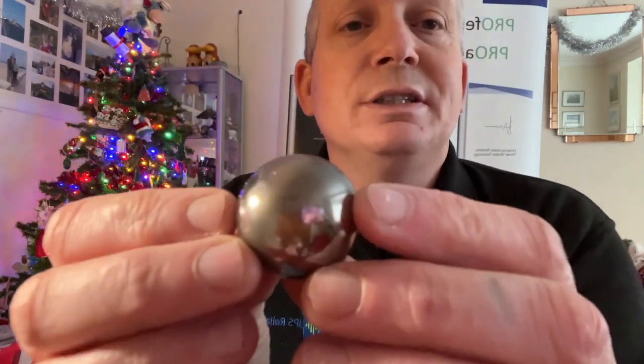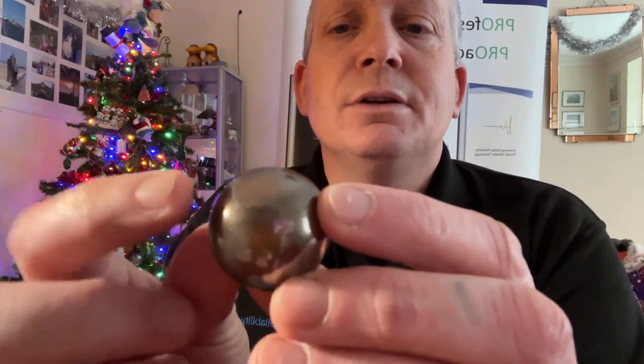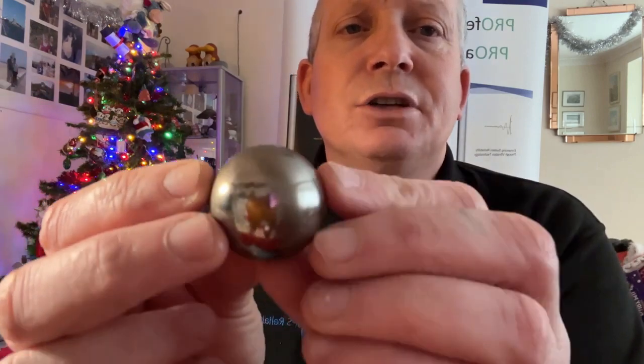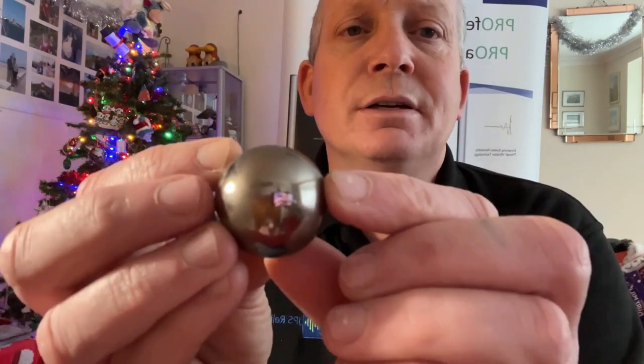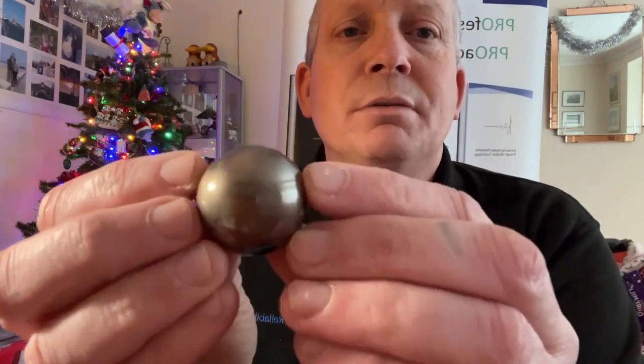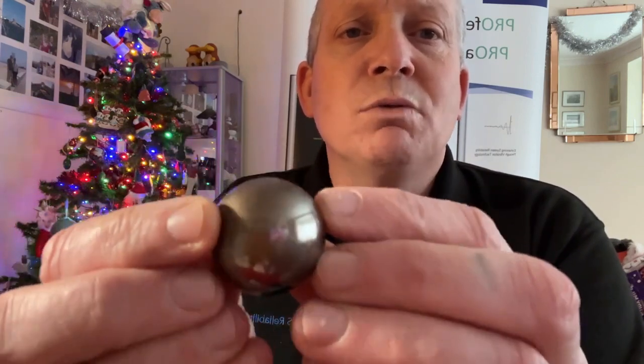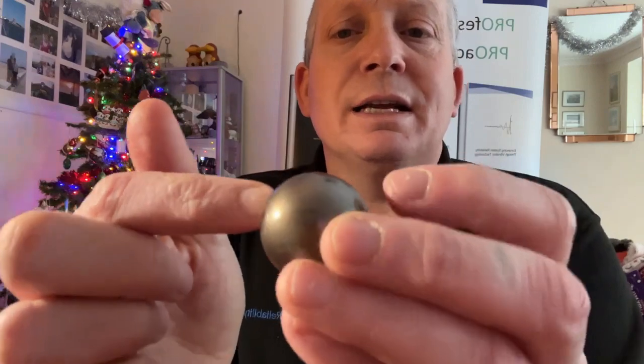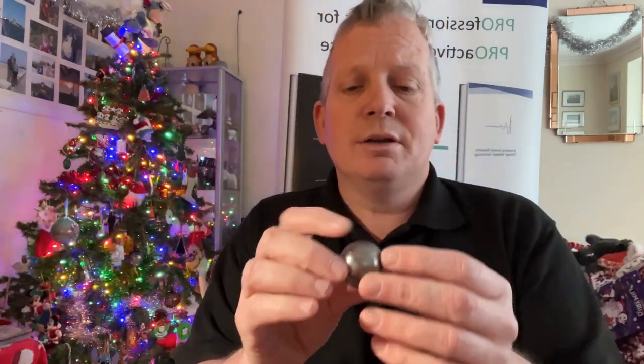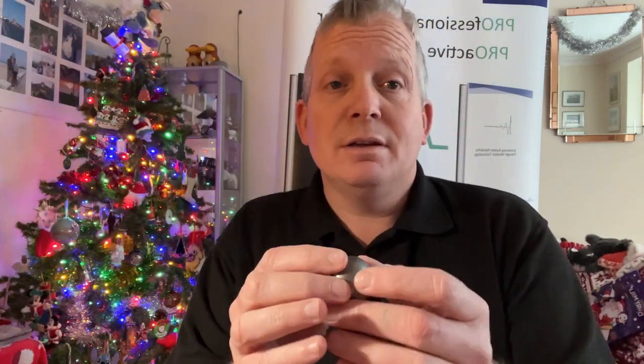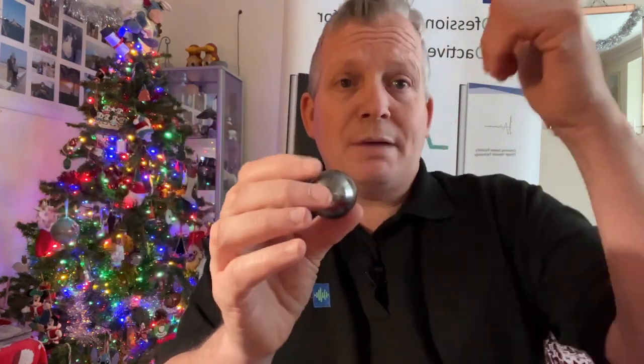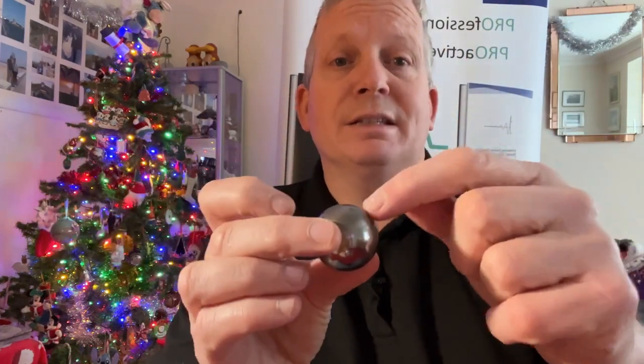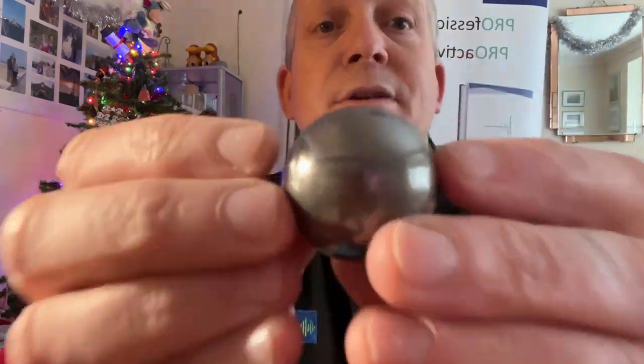Okay. Now, another giveaway if you've got drive problems or challenges: if you look at the rolling element here, you can see it's shiny there, but then look at this bit here. It's got a row of dullness. That dullness is the electrical high frequency current, noise, whatever you want to call it, trying to get back to your start point, your transformer, and the quickest way is through the grease and through the bearings. So you get that shiny and dullness.